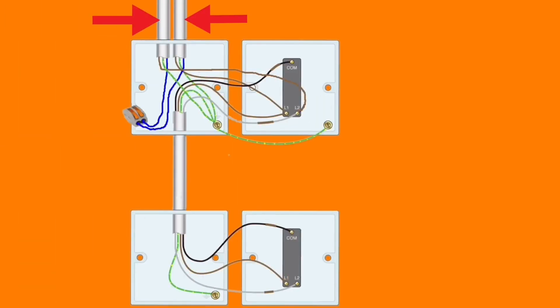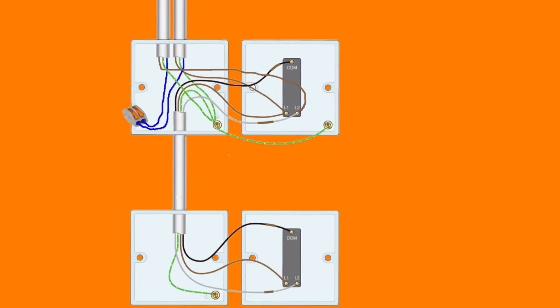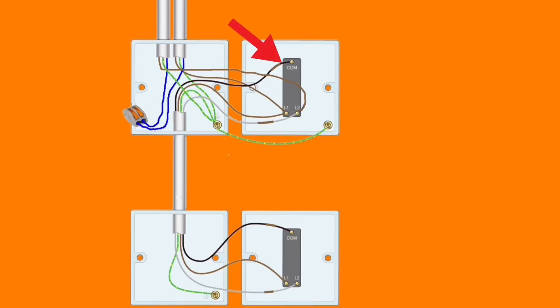To convert this to two-way switching, the conductors coming into the top switching point are identical as before - a supply coming in carrying line, neutral, and CPC, and one going out which is the switching line, neutral, and CPC. We've replaced the one-way switch with a two-way switch. Our two brown conductors, previously in common and L1, have now been reattached to the two-way switch going in L1 and L2. We've introduced the three-core cable connecting this two-way switch with the new two-way switching position, using black for common identified with brown sleeving, brown in L1, and gray - also identified with brown sleeving - in L2.